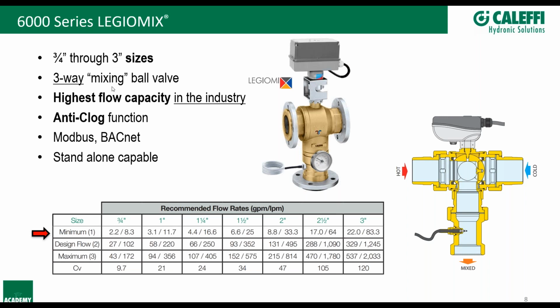And I will caution you very highly on this. If you are using a three-way ball valve assembly, you're going to get really high flow rates with really low pressure drops. Okay, so it's very easy in a lot of cases to oversize these mixing valves, and I can't stress it enough. And most of you guys are probably, if you're on this webinar, you're trying to continue your education, you're trying to do best practices and everything else. And best practice with sizing these mixing valves is to size them based on the flow rate and pressure drop going through them, not by pipe size.